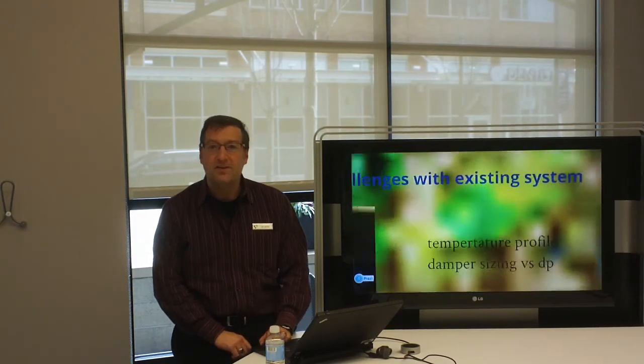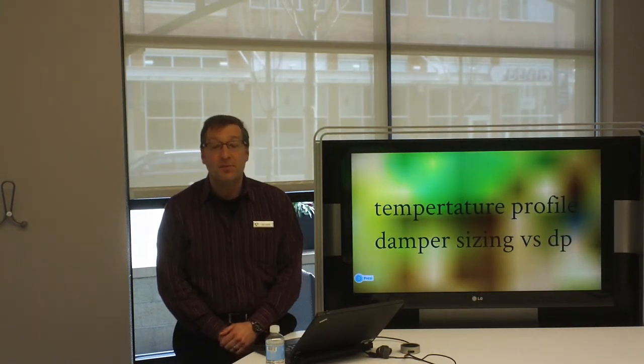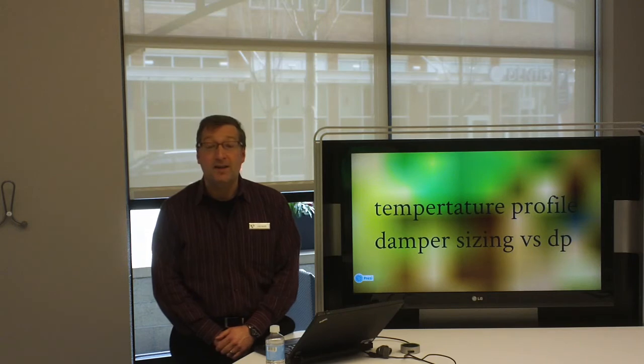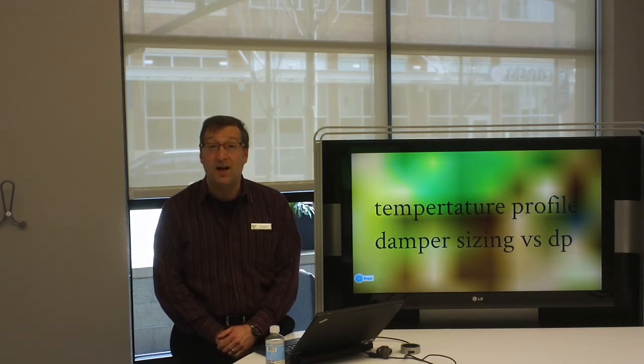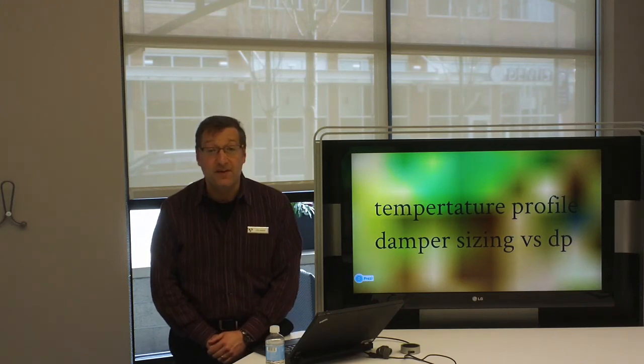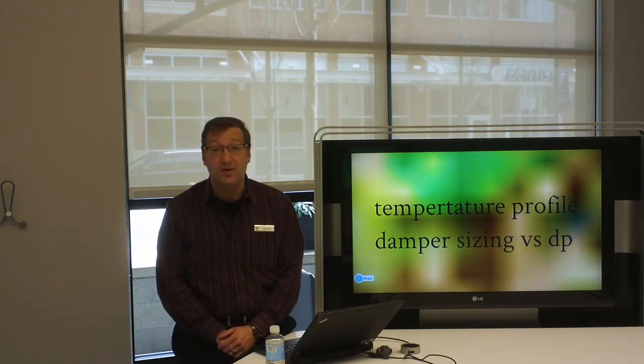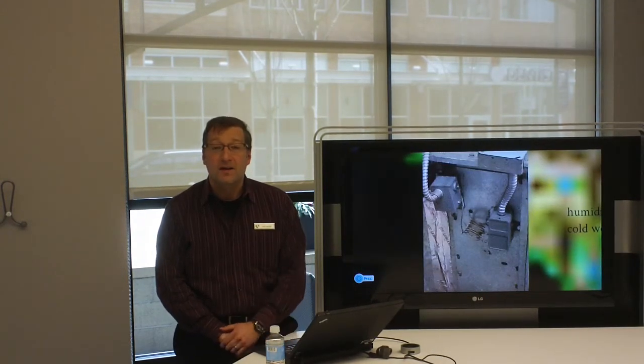Additional challenges: the temperature profile proved that we were not getting a good mixing in the mixed air chamber, and that we had stratification. This could, in fact, be one of the causes of the freezing damage. The other thing we noticed, based on the damper sizing and the differential pressure, was that we felt the dampers might be oversized. This is a picture of the freeze protection.